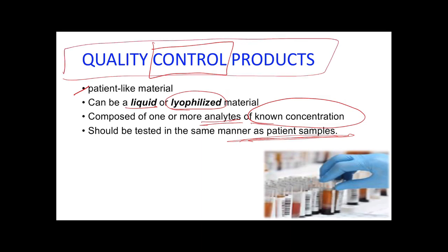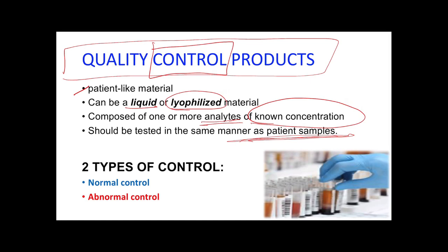The purpose of the quality control product is to validate the reliability of the test system and evaluate performance in the analytical phase. There are two types of controls: normal and abnormal control. Abnormal controls can be abnormally high or abnormally low. Normal control contains normal levels of the analyte, whereas abnormal control contains the analyte at a concentration above or below the normal range. Good laboratory practice requires testing both normal and abnormal controls for each test at least daily; some laboratories test controls per shift.